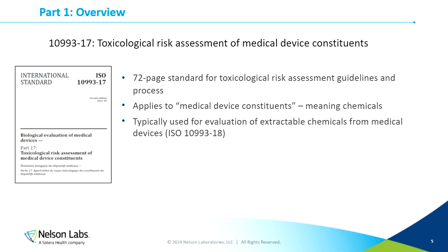It turns out that this standard is actually a fairly intimidating standard. It was updated last year in 2023. It's 72 pages, and it's quite in-depth. The purpose of this standard is generally to address what they consider medical device constituents. To me, that just means chemicals. And typically, this is applied to extractable and leachable medical devices.